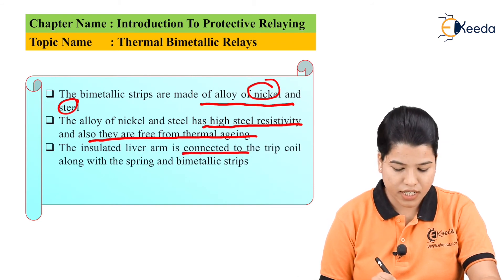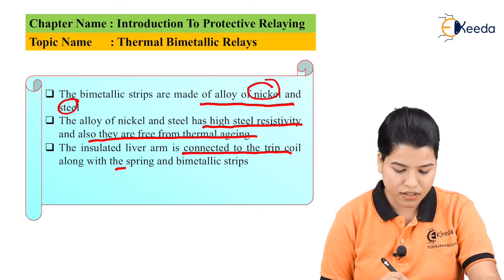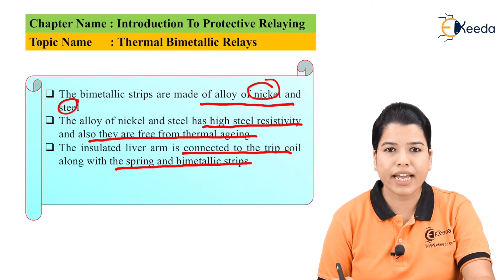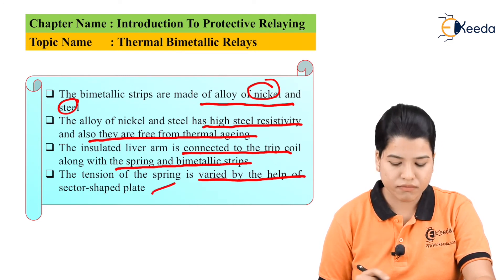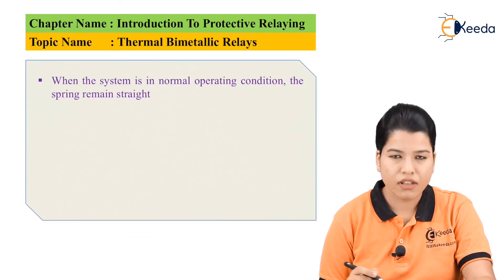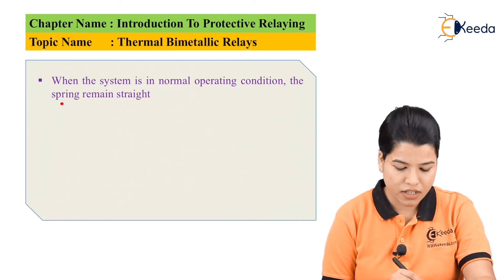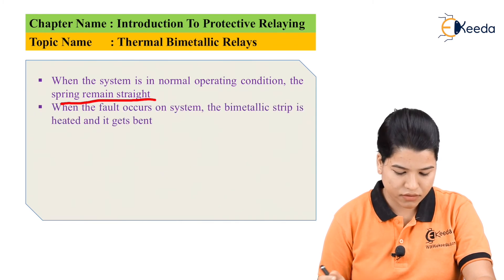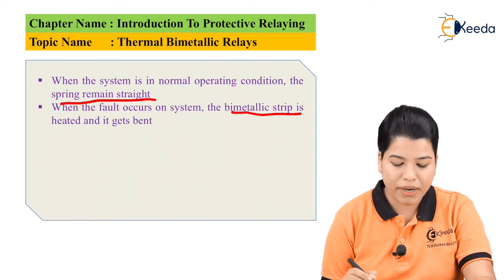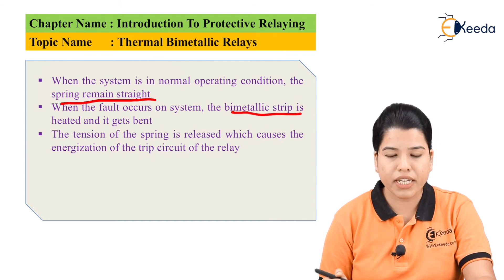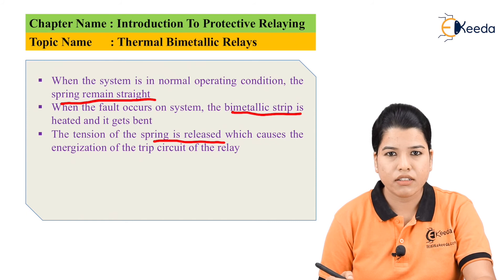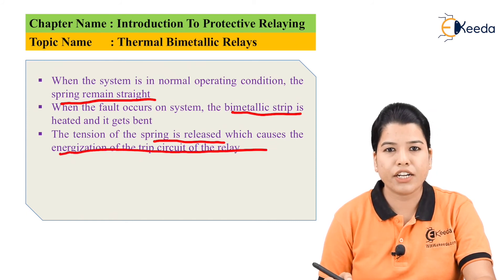The insulated lever arm is connected to the trip coil along with the spring and bimetallic strip. The spring holds the insulated lever arm away from the trip circuit under normal operating conditions, and the tension of the spring is varied with the help of a sector-shaped plate. When a fault occurs, the bimetallic strip gets heated and bends, releasing the tension of the spring and causing energization of the trip circuit of the relay.